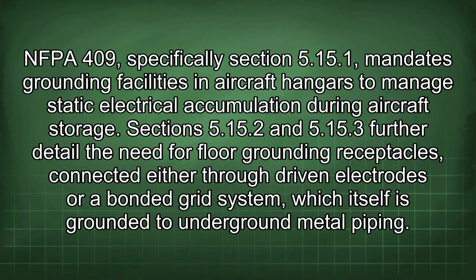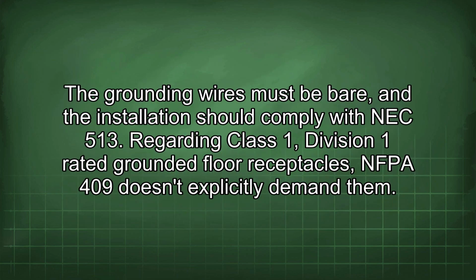NFPA 409, specifically Section 5.15(1), mandates grounding facilities in aircraft hangars to manage static electrical accumulation during aircraft storage. Sections 5.15(2) and 5.15(3) further detail the need for floor grounding receptacles connected either through driven electrodes or a bonded grid system, which itself is grounded to underground metal piping. The grounding wires must be bare, and the installation should comply with NEC 513.